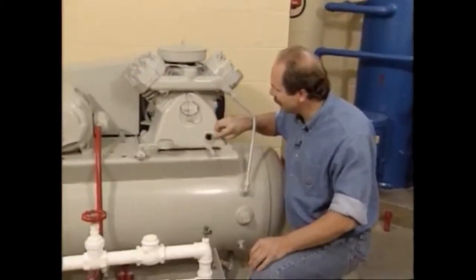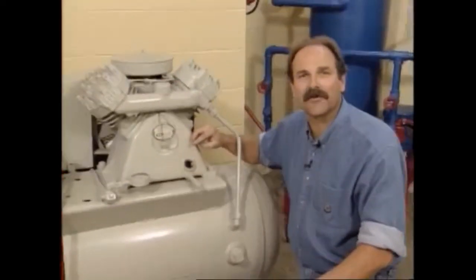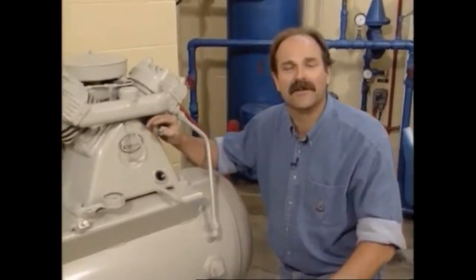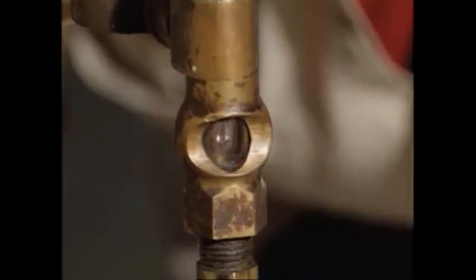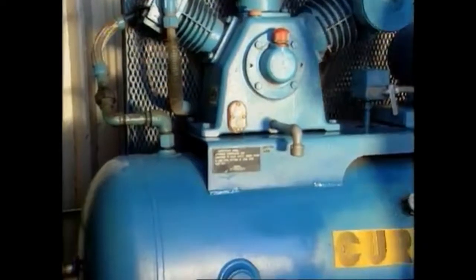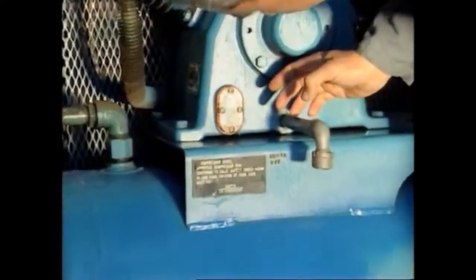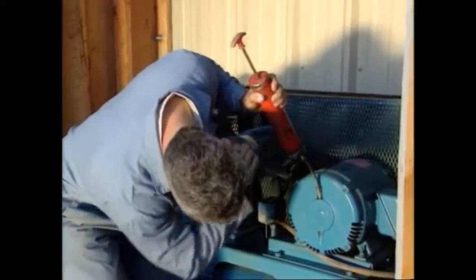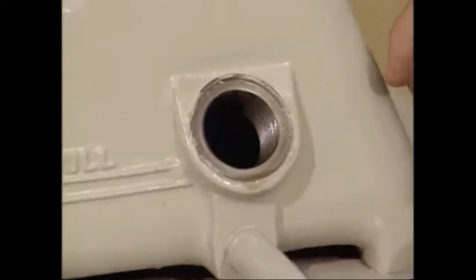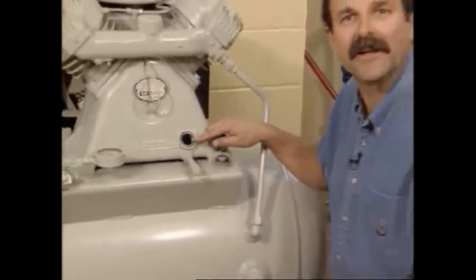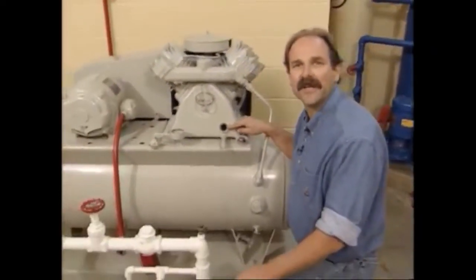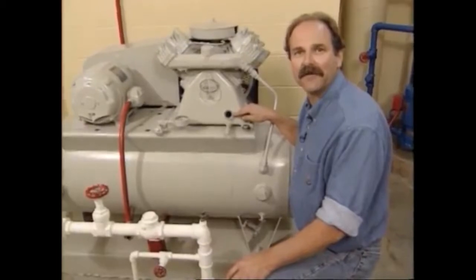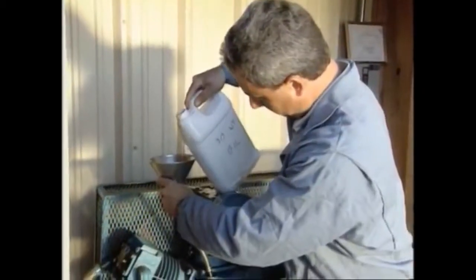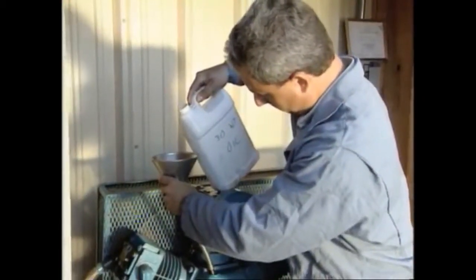Inspect the reservoir level or sight glass if so equipped. Also, if your compressor has a drip type system, make sure that the drippers are dripping at the proper rate. Be sure also that the force feed oilers have the proper pressure and grease fittings are greased at the proper interval. Compressors use a certain amount of oil in their daily operation. Make sure that you check the reservoir level to keep them full. Care also must be taken not to overfill the crankcase.